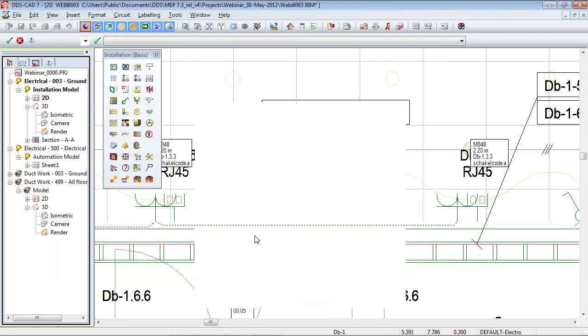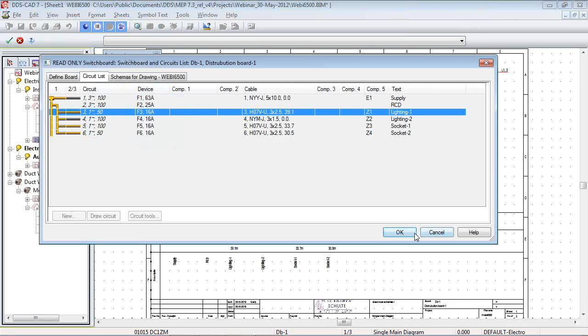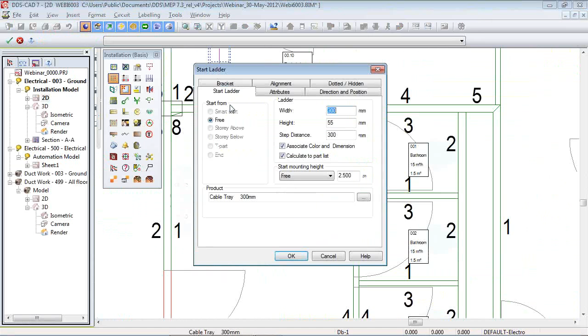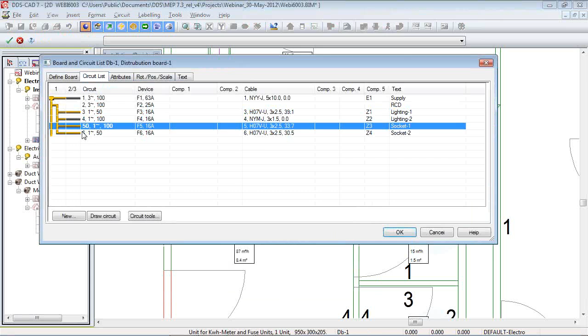In this case, a 1.5 could be available, but by local regulations we may need a minimum of 2.5. Together with the cable installation method, we can calculate how this cable will react in an overload situation. This is a situation connected to a wall, and this kind of information comes directly from DDS itself.